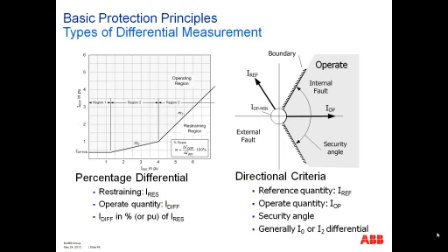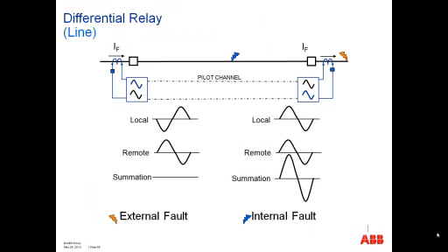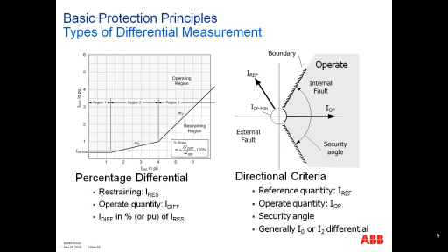You also have different types of differential measurement. One is that you have some type of restraining quantity, and the restraining quantity is plotted against some difference quantity, and you have some slopes. You have a minimum operate level of the slope. Then I show a lower slope, which is referred to as M2, and a higher slope, shown as M3. And that shows you the basic difference between the restraining region and the operating region for your IDIF compared to IRestraint. And then you have another one, which is sort of a directional criteria, where your I operate is compared by angular relationship to the reference quantity, IREF. Okay.